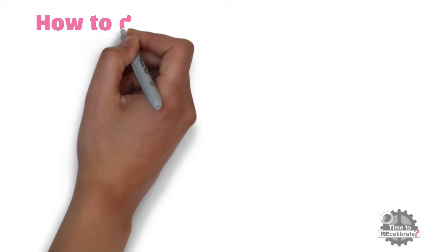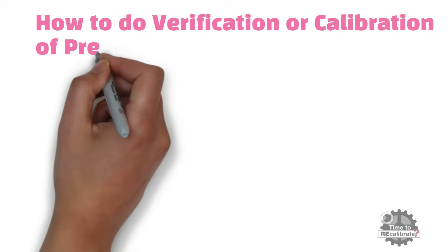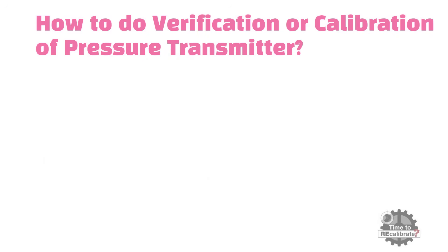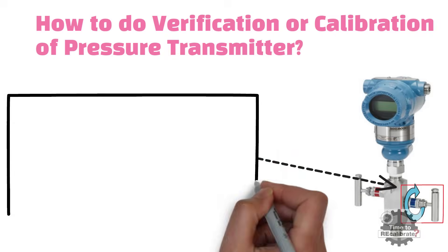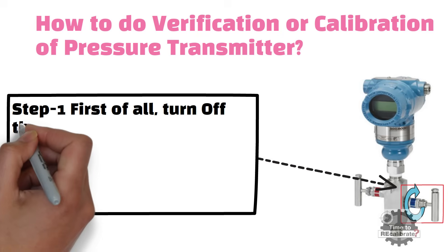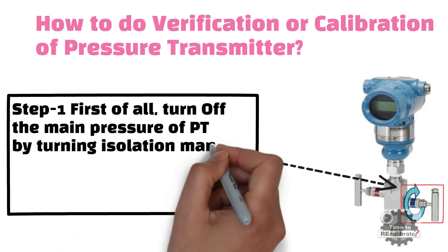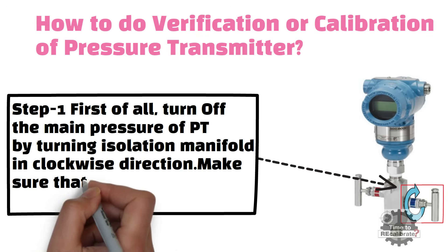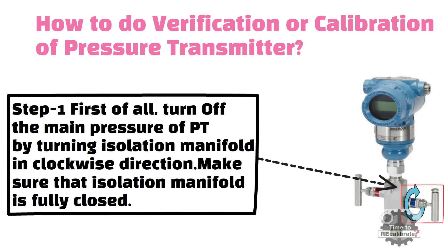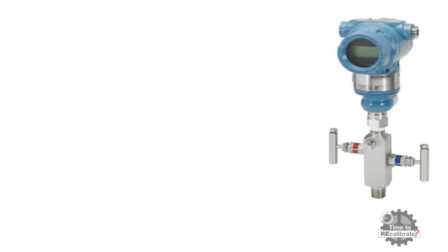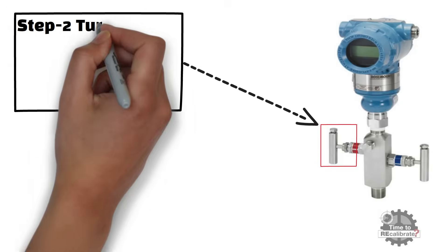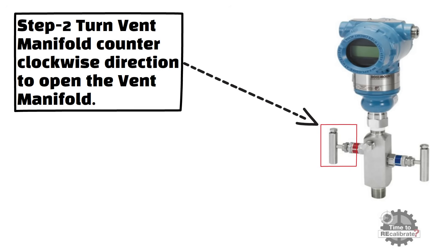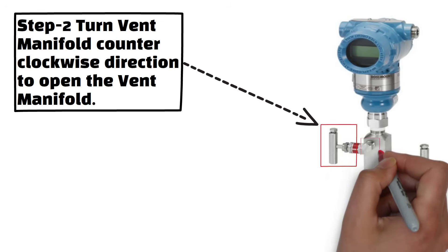How to do verification or calibration of a pressure transmitter. Step 1: Turn off the main pressure to the pressure transmitter by turning the isolation manifold in a clockwise direction. Make sure that the isolation manifold is fully closed. Step 2: Turn the vent manifold anticlockwise in order to open the vent manifold.